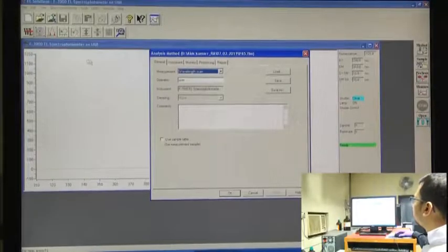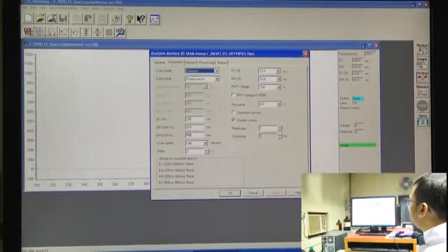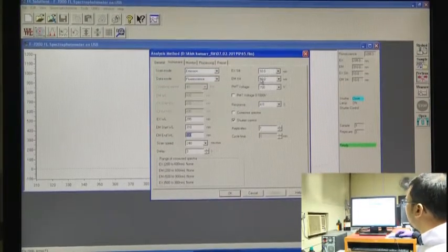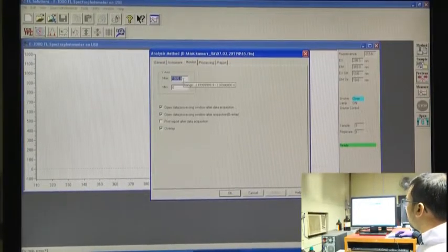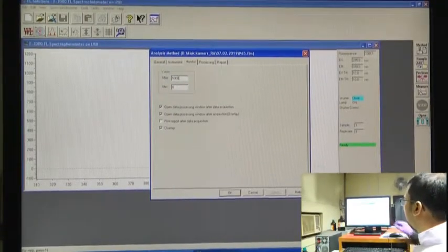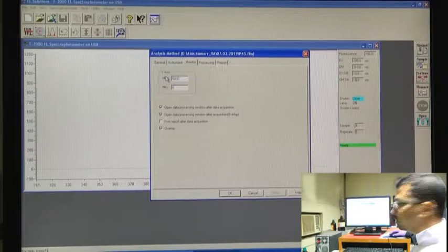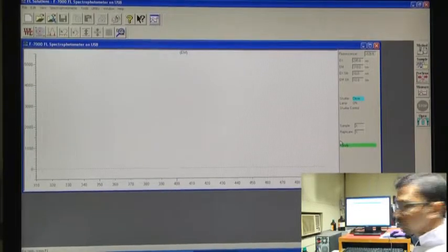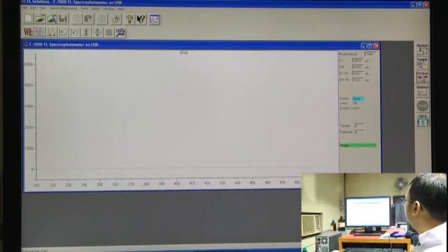and close this lid. Now, here we have to go to method again, and here we can see the excitation wavelength is the same, 295, that is for tryptophan. The emission wavelength starts from 310 and ends at 500. The scan speed is 240 and excitation and emission slit bandwidth is 10 nanometer, and we will change this maxima to something around, suppose, 5000 for the y axis, and we will click OK. Parameter initialization has occurred. Now, you will do pre-scan.